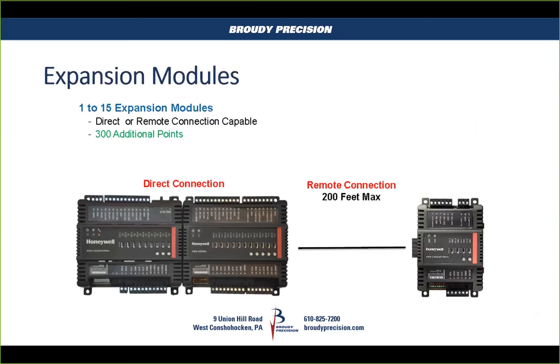But this can be plugged directly in the side of the CIPer, as shown here on the left side. That's a large one plugged into the side, or you can plug a 6-position terminal strip in the side, and you go up to 200 feet remotely for remote I/O if need be. And I think that's the standard range on panel bus. Yeah.